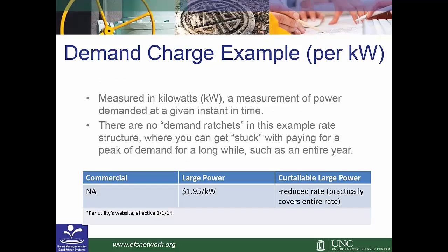So, an example of a demand charge, again typically measured in kilowatts, kW. It's a measurement of power demanded at a given instant in time. Now that instant, as I said, may be 15 minutes, 30 minutes, or an hour, but it's not the whole month or the whole quarter.